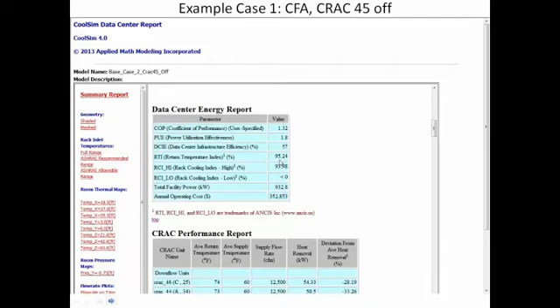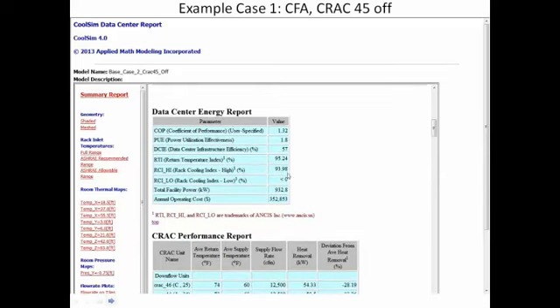Because in an N+1 design, we usually have more air than we need because we've got an extra unit running in case one fails. So when we take one of them down, and in this case I took one of the 20 tons down, the RTI actually improved, but look what happened here to the RCI. It came down. So what that is telling us is that now, even though our RTI is going up, we have a better balance of airflow, total airflow compared to total demand or need by the racks.